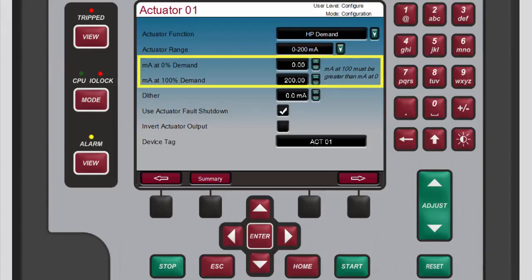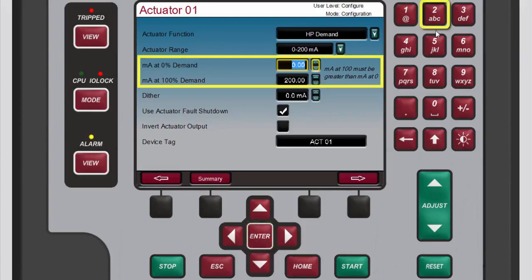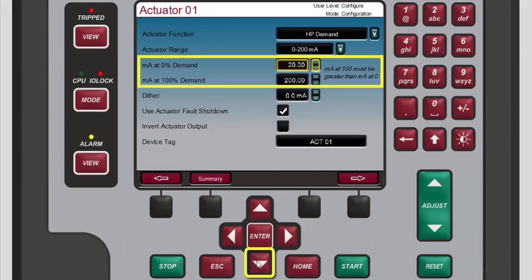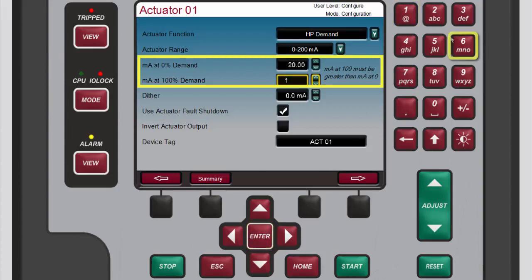To set the zero to 100 percent demand for the next two boxes, set the current at either end of the demand spectrum. For example, for an actuator that requires 20 to 160 milliamp, enter 20 in the milliamp at zero percent demand box and 160 in the milliamp at 100 percent demand box.